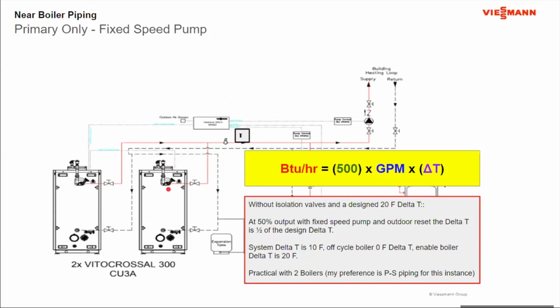Now, since outdoor temperature drops, the water temperature out to the heat emitters also will be half of what it is on the design day. So if I drop this in half and the gallon per minute is fixed, then the delta T has to be cut in half as well. So on a design day, my delta T here may be 20 degrees, but on that 35-degree day, the delta T here is only 10 degrees.